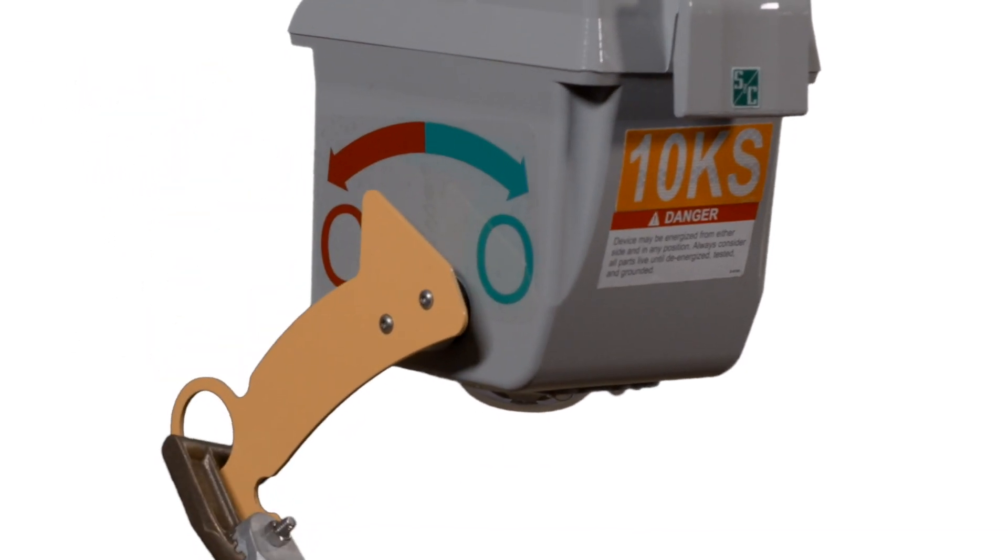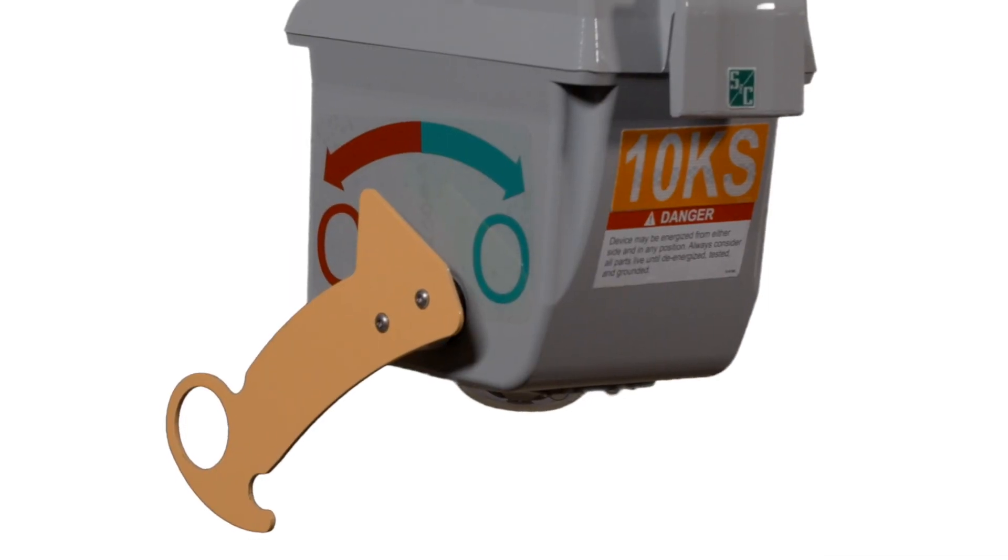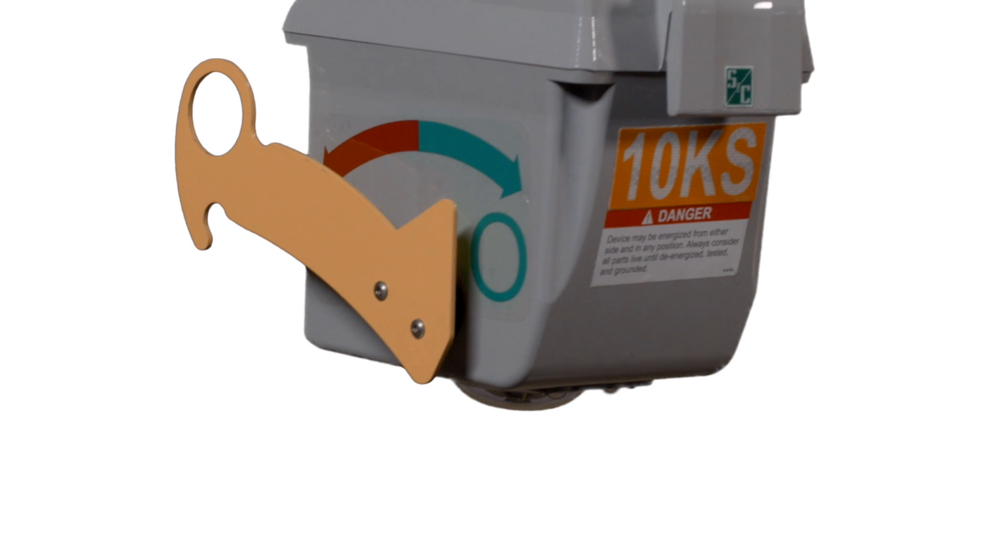In the event the VacuFuse self-resetting interrupter is closed into fault current, the interrupter will immediately trip open. This will put the open-close lever out of sequence with the position indicator. The lever will indicate closed while the position indicator shows open. The lever can easily be put back into sequence by operating it into the open position by pushing up on the indent in the open-close lever.